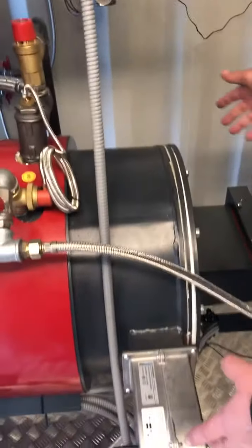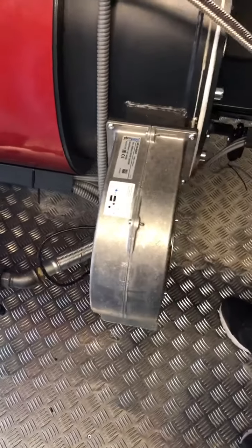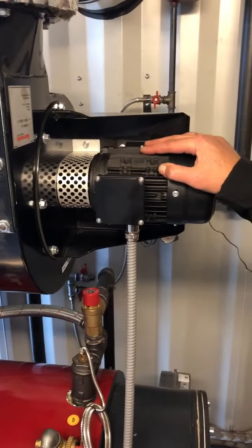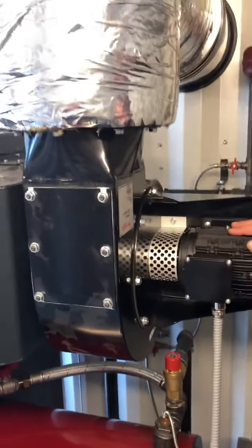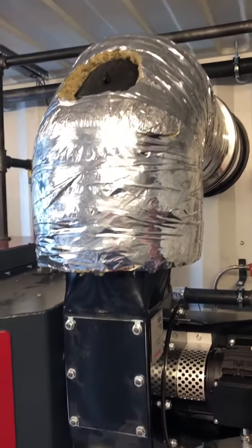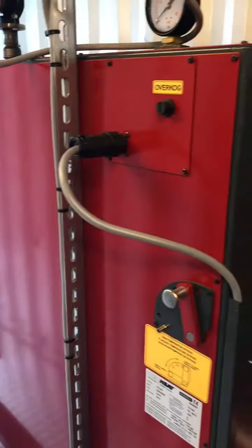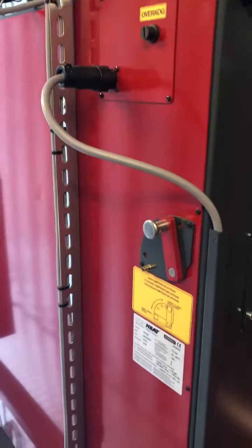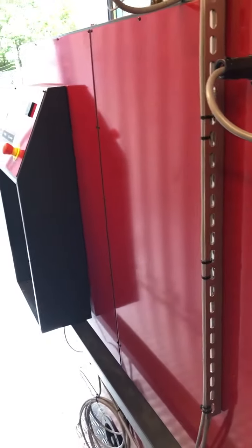Here we have the 2 combustion fans for the burner tube. It depends on which model it is, but this is CS150. Got 2 fans on. Here we've got the fan for the exhaust. It's controlled by a regulator on the control panel, and it measures the pressure, the under pressure in the boiler, in the door end, in the side of the boiler.